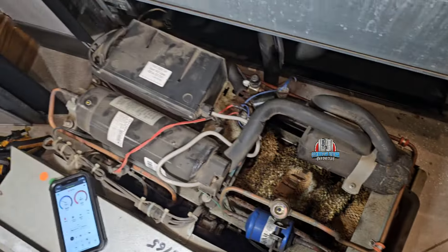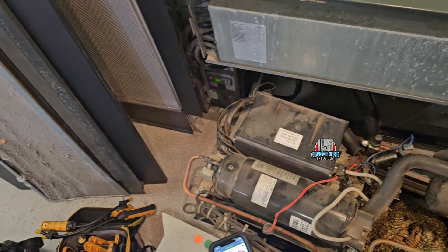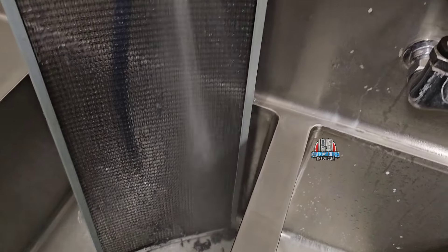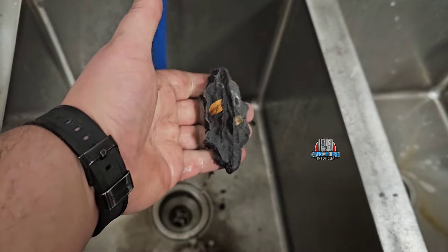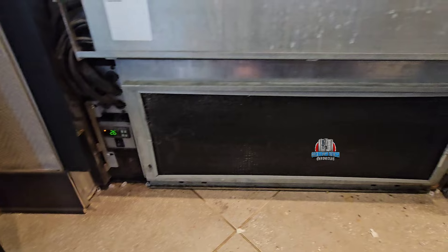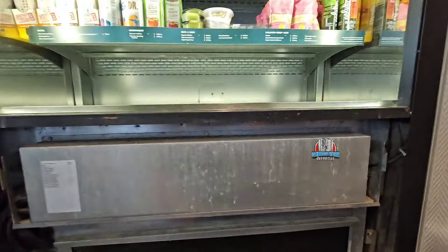There's oil on the rail, all the way across here, oil on the floor. I mean it's running, the sight glass is still flashing, but I'm out of R-404A. It's dropping though. Sprayed it back together — 26 and dropping. I'll be off for a little bit, clean that out. I'll get it loaded up, put it all back together, get the quote submitted.